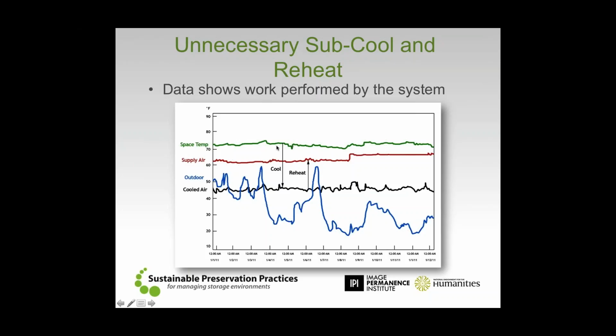Well, as the space temp goes back through the loop and back to the unit, what's the first thing that we do? Well, it hits the cooling coil, and it gets cooled all the way down to 45 degrees in the middle of winter, when there's nothing to dehumidify out of that air. So first we dehumidify, or we cool all the way to 45 degrees. Here's my subcooling that should happen in summer. And then as the air moves downstream and hits the heating coil, we reheat it back up to 62 degrees before we then send it back out to the space.